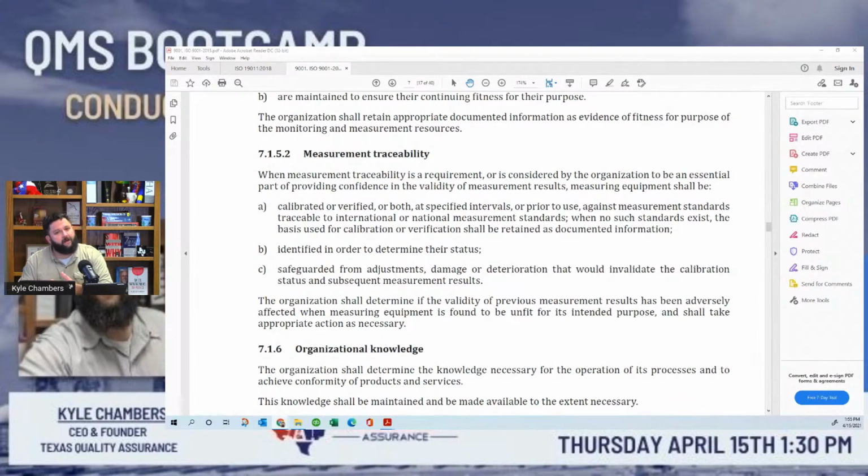Well, why not? And the answer could be that the equipment itself has a self-calibration going on. Great, fantastic. Maybe it's the case that extreme weather fluctuations are all that would affect the equipment, that the temperature variations in an office facility aren't sufficient. Great, that's good information. On the other hand, if you say, yes, this is a requirement, well, then I can start to ask, well, what controls do you have in place? And this can lead us down a very, very different path.